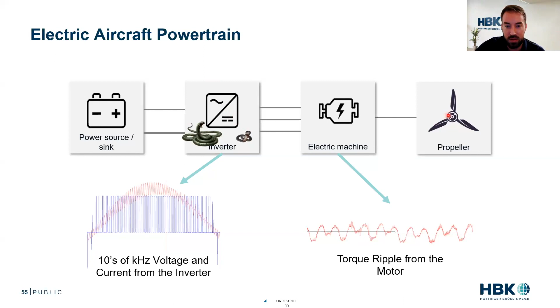And just to back that up, if we look at some data from a motor, with current in red, torque in black, and vibration in blue, HBK actually has really awesome torque sensors where you can see torque ripple up to 6 kilohertz. We just plot the simple FFT, again from our software. We can see our current and some of our current harmonics, and then our torque ripple and our vibration really lining up. This is what we're afraid of for things like whirl flutter.